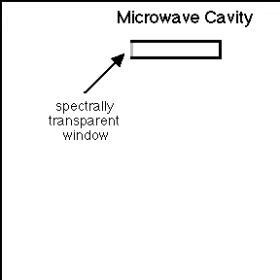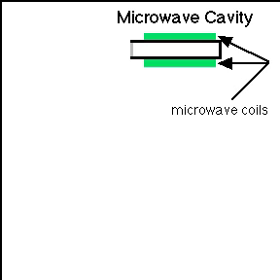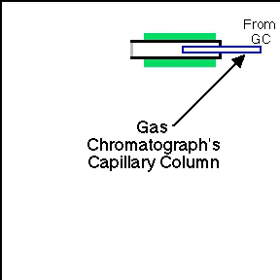Chemical analytes that exit the capillary column flow into the discharge chamber along with the carrier gas, and sometimes even additional reagent gases, plumbed in via auxiliary gas lines.